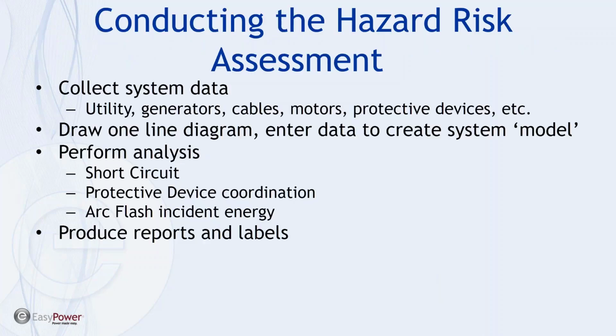So as we're calculating arc flash and collecting data, we need to keep that in mind, because the data that we're collecting has bearings in several different respects. First of all, we're calculating or developing the impedance of the system from the source to every particular load. We're looking at the contribution from each of those points to any given bus fault. And at that point, once we've determined what the fault current is, what the fault current would be if that were an arc that were creating the fault, and then finally, how long it's going to take to terminate or extinguish the arc.